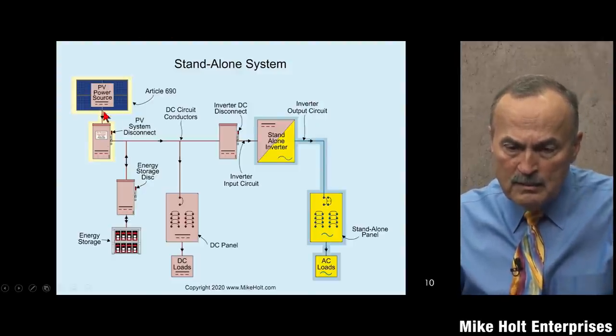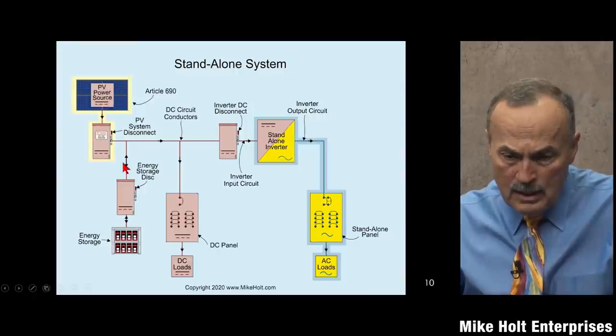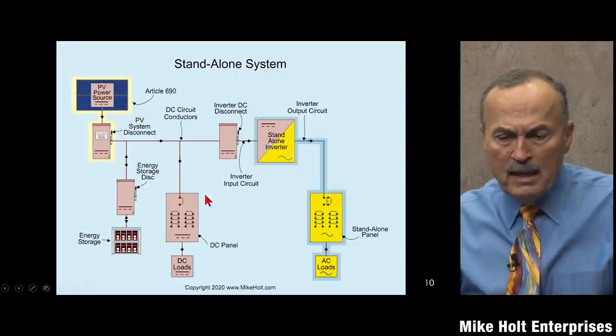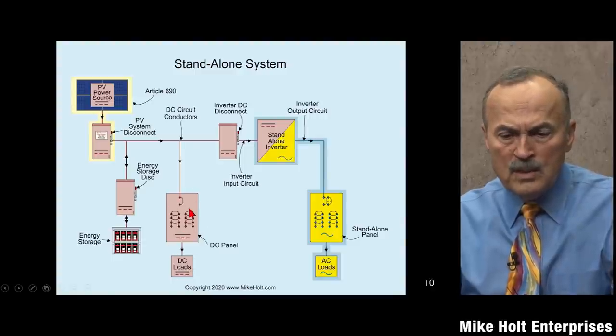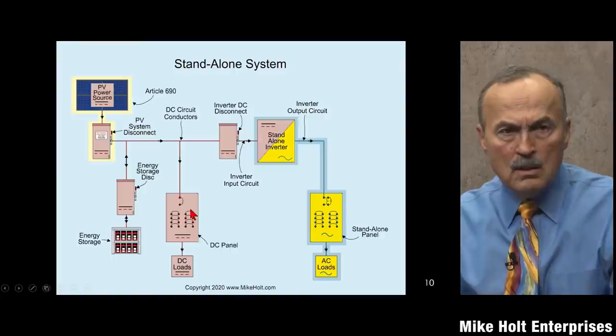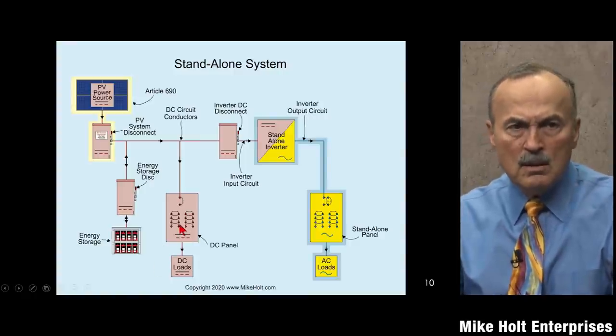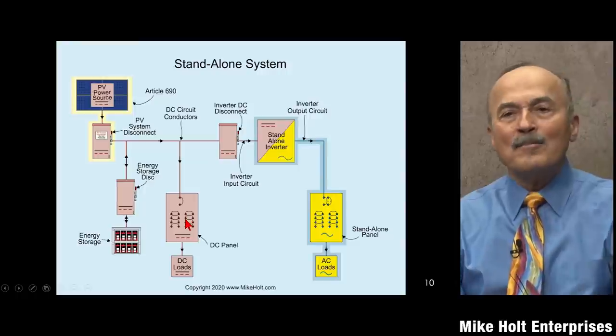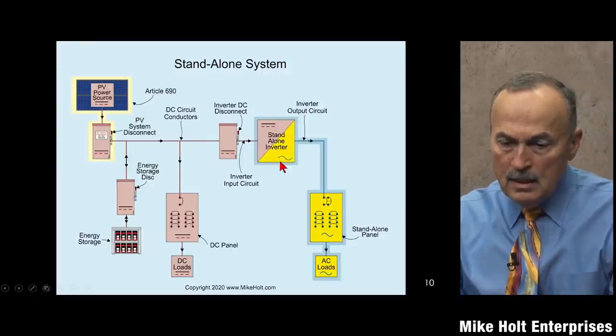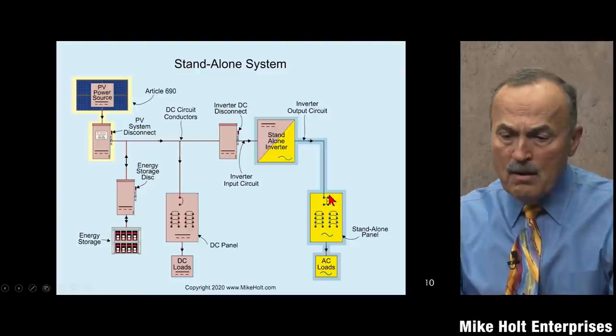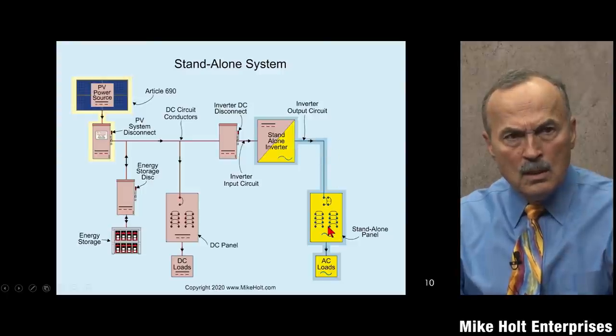Now: Article 690 ends at the disconnect. Energy storage is Article 706. Standalone is Article 710. Previously Article 690 had all those things combined, which was very difficult. Now different articles address the unique conditions of each system type. In a standalone system, electrons can go both ways through the energy storage. You can have DC panels with DC loads - standalone systems could be 12 volts, which is common in the RV industry.